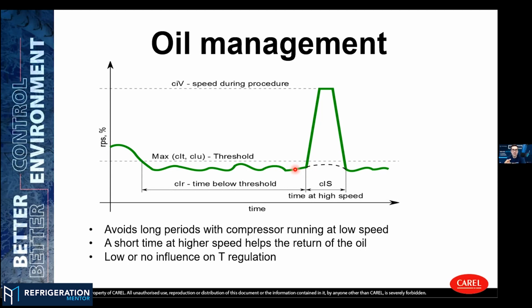But what I would like to know is, does it have to run for 2 hours at less than 25%? Is there an idea? Because when this is going to happen is when you're not there. These are low load situations in the middle of the night. The doors are shut, no product is being put in there, right? That's when you run into this oil management ramp up. Yeah.